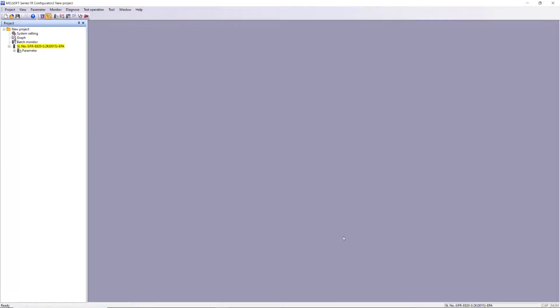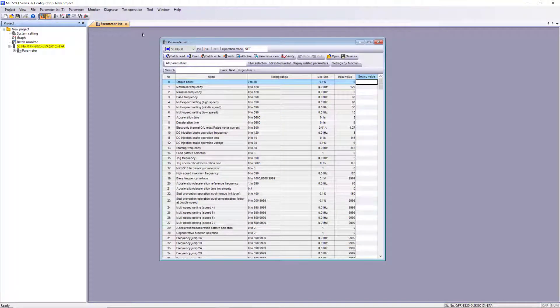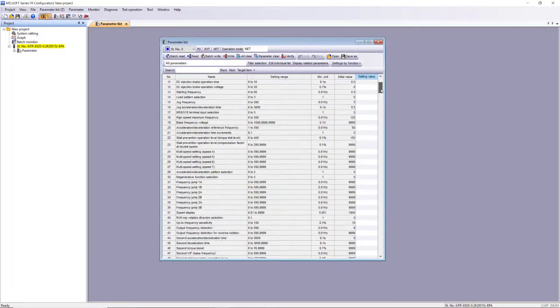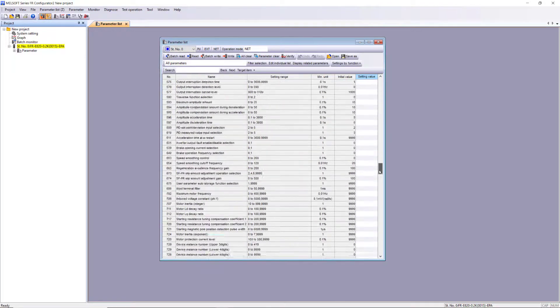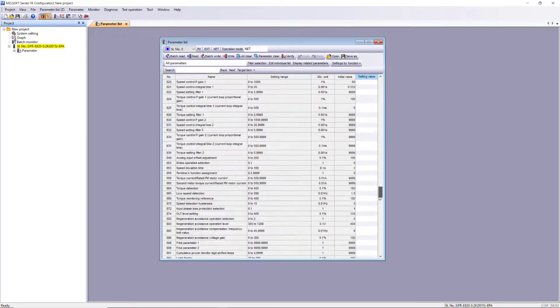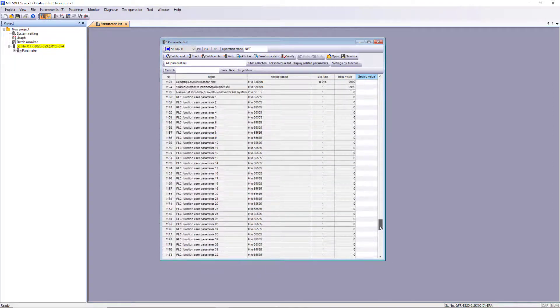After the project is created, select this button to go online with the inverter, and then the parameter button to bring up the parameter list. Scroll to parameter 1434, and you'll see the inverter's default IP address and subnet mask.